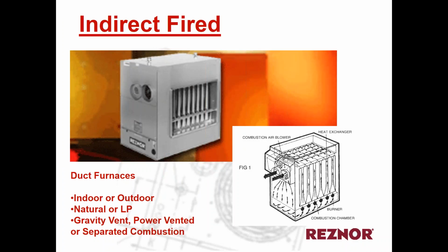This is a view of our duct furnaces. We make lots of duct furnaces from 100,000 BTU input up to 400,000 BTU input, and they're still used in new jobs and replacements. And essentially, it's what the name says. It's a duct furnace. It's a unit that is going to be used with an external fan or air handler to provide heating into a duct system or a ducted system. They can be made either indoor or outdoor, natural or propane, and gravity vented, power vented, or separated combustion. What you'll see here is one of our separated combustion units, which once again brings air from outside for combustion and then power vents the flue products out through an approved venting kit.